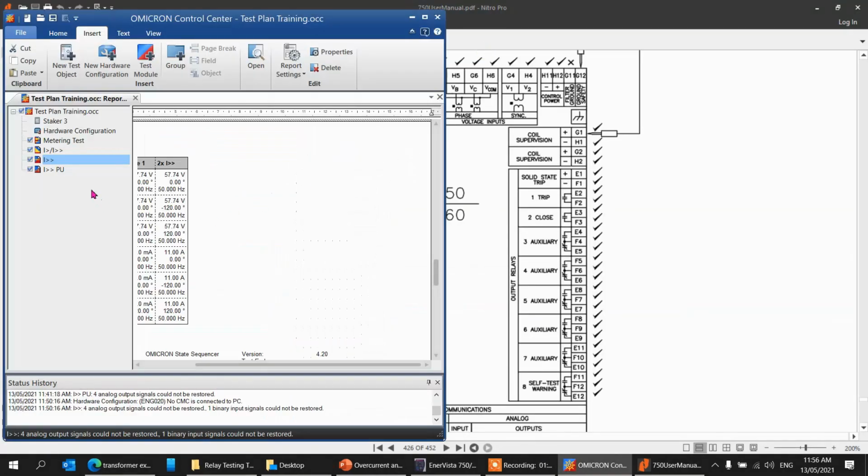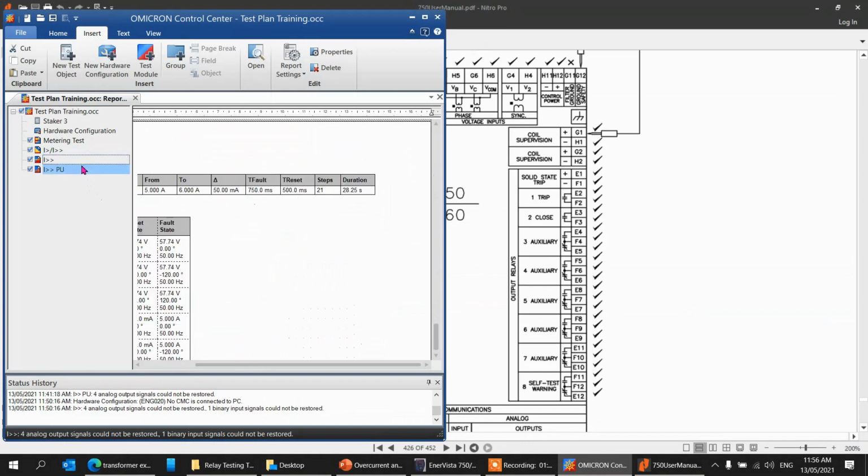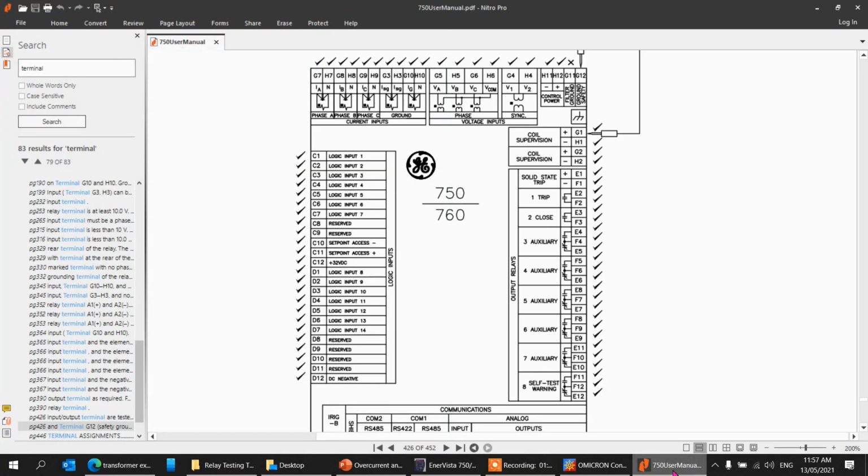That's most of the basic one, and it's up to you, because sometimes testing depends on how you understand the behavior of the relay. How would you start the testing for you to be satisfied that this is okay? Number one, you have the documents, the drawing, and this one here. You can see if you connected those terminals properly, the current, the voltage.